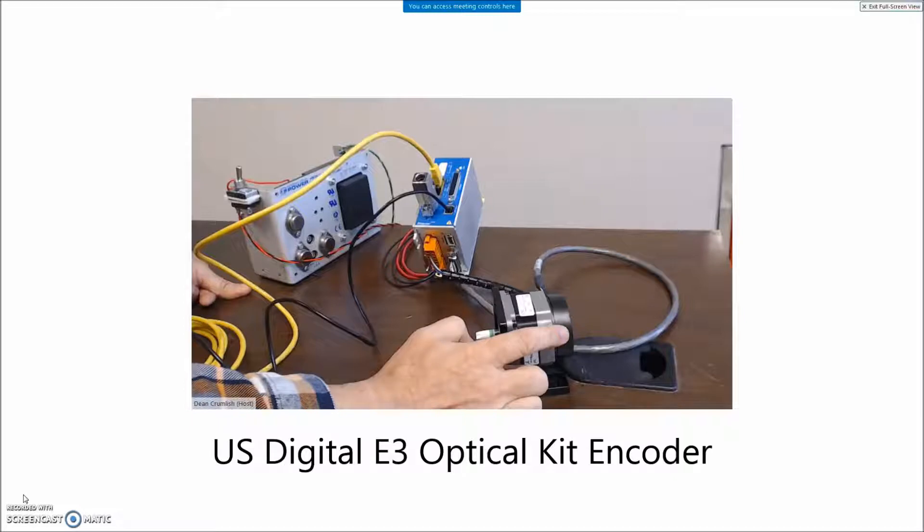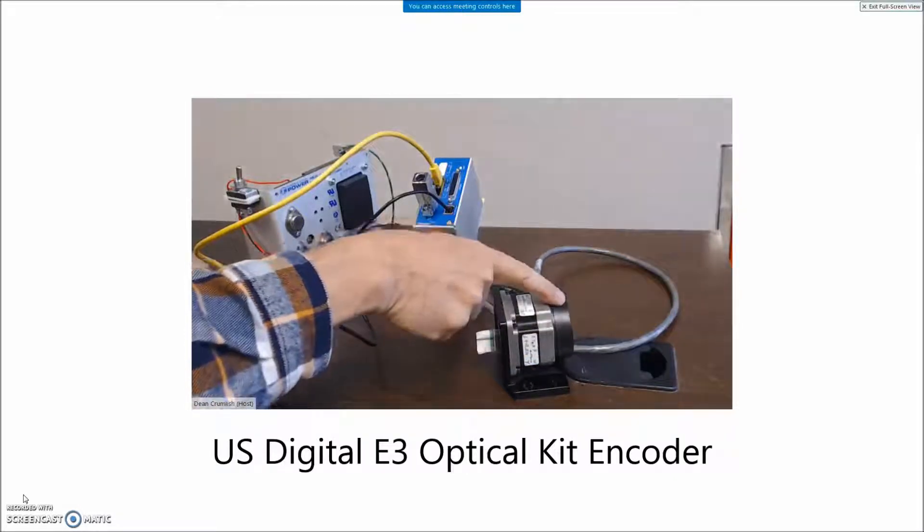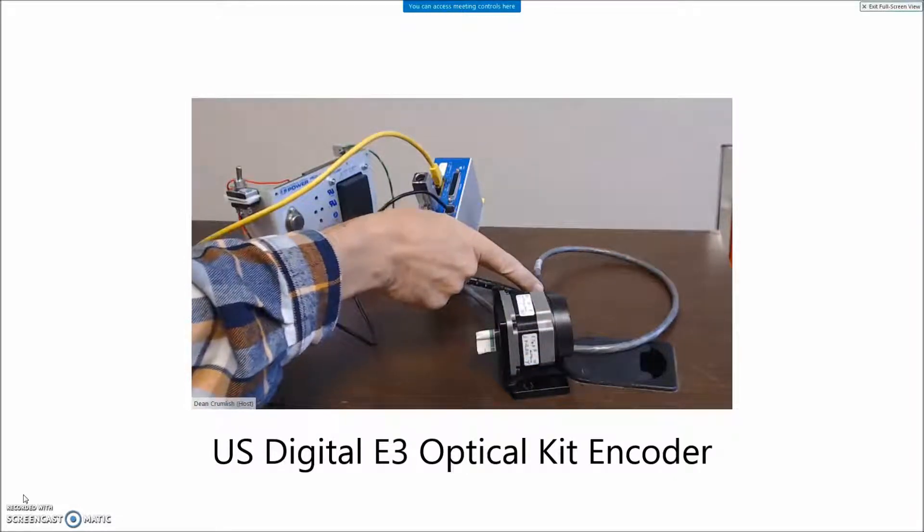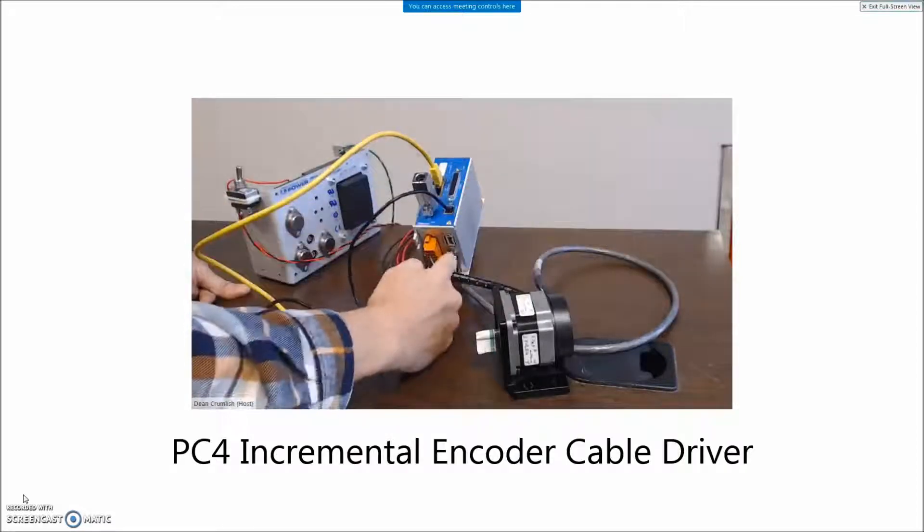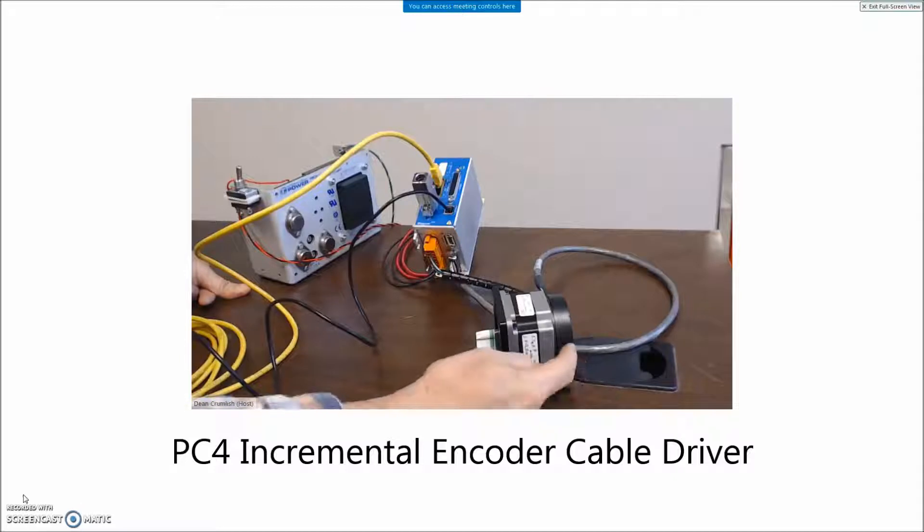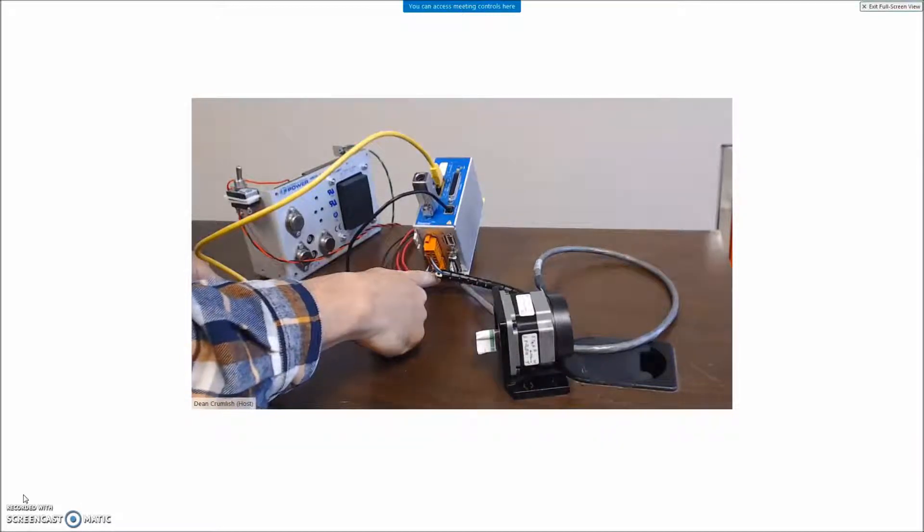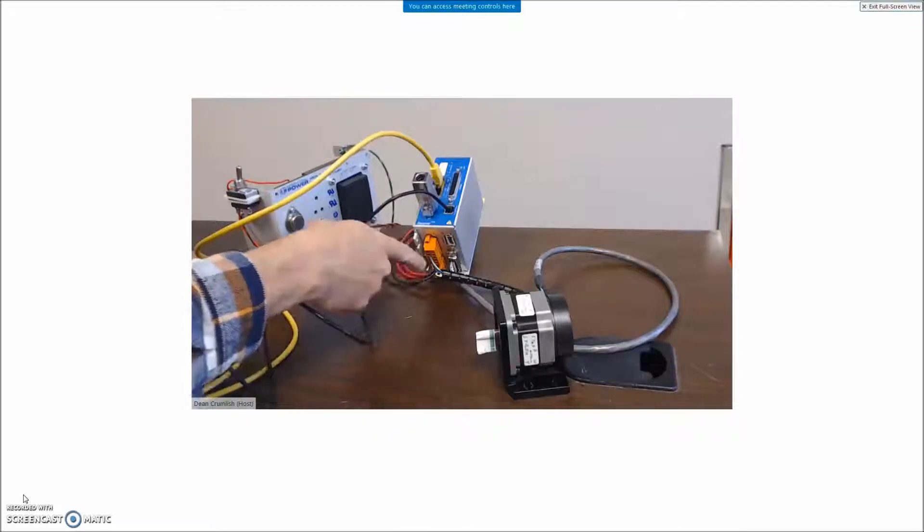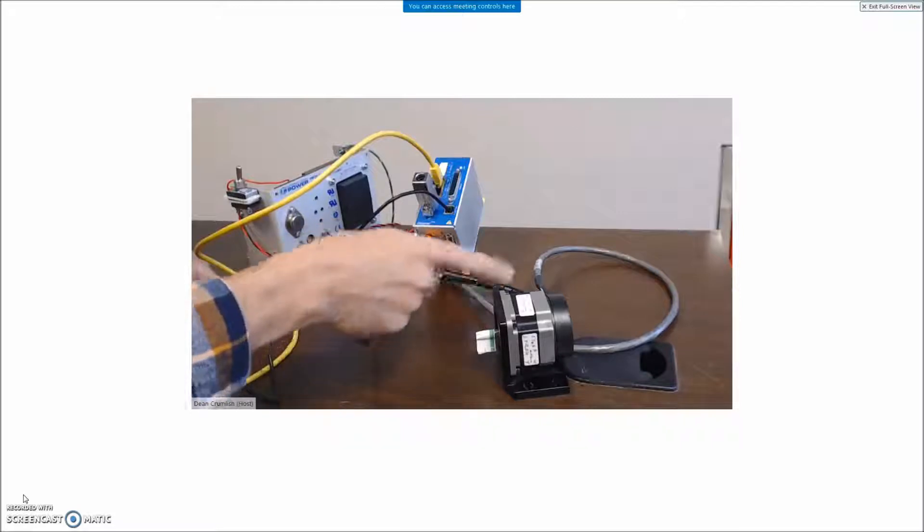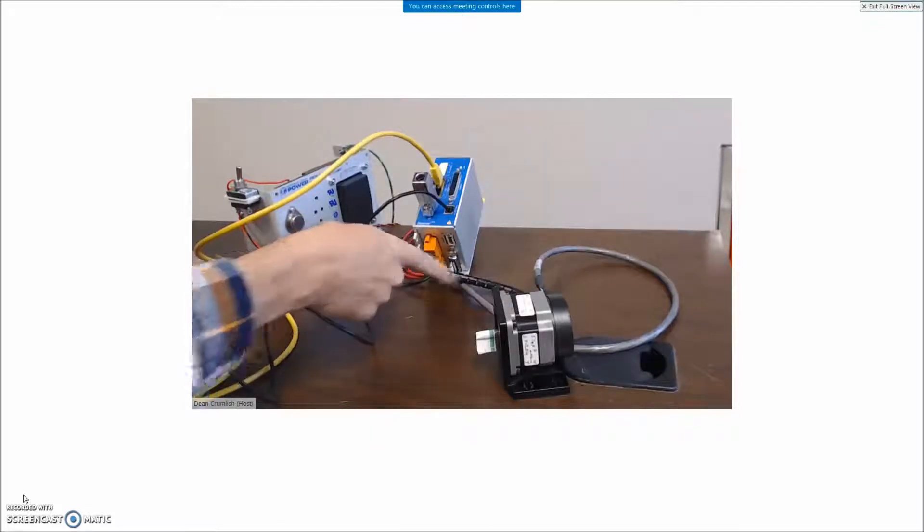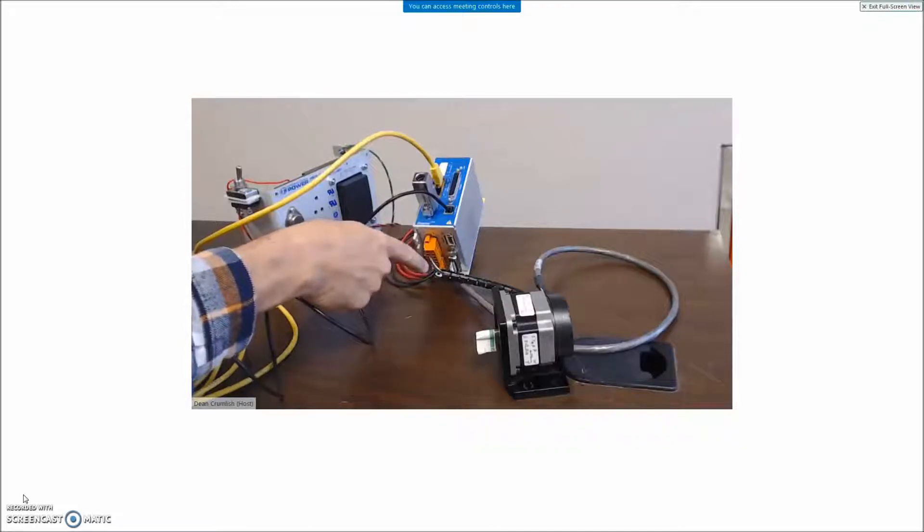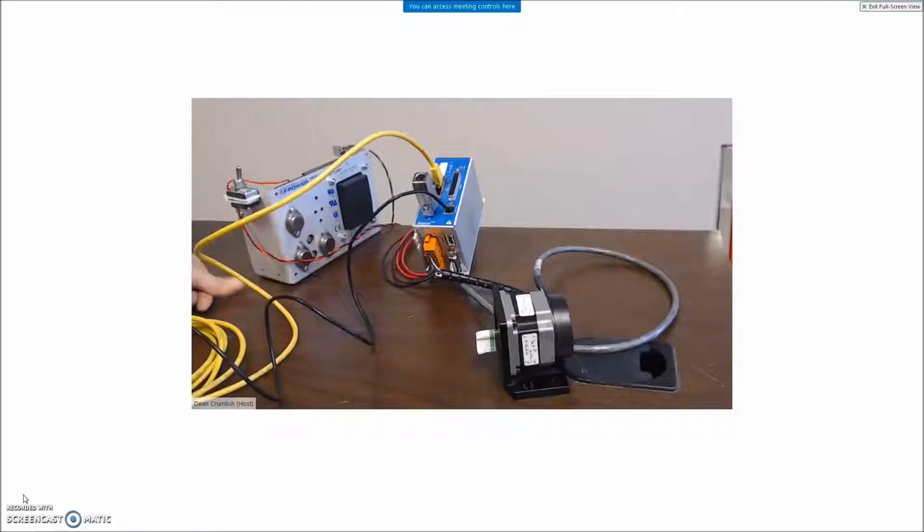On the back here I have a U.S. digital encoder single-ended to differential adapter and then a cable which I've got wired to the feedback. So this does have an incremental encoder 4000 line. I got the motor power connected. We should hook up earth to the frame of the device. I got the motor four wires hooked up and I left the center taps open so that we can get the most current into this motor. That should be sufficient to do 60 RPM today with no problem.